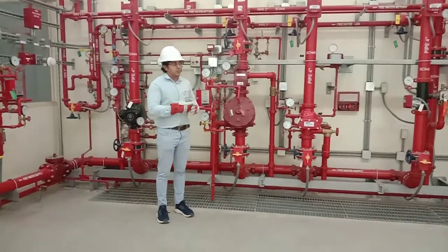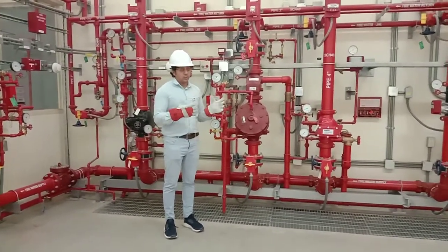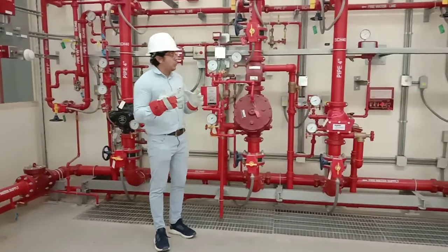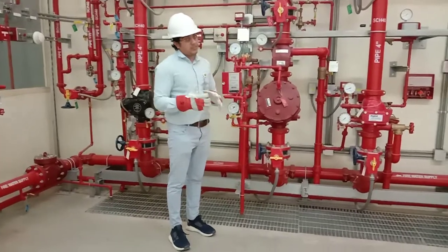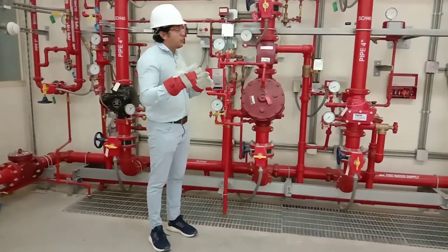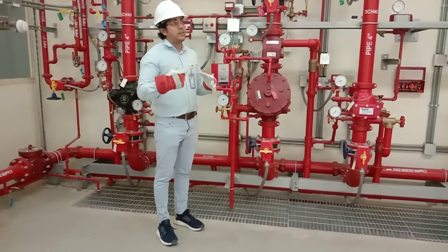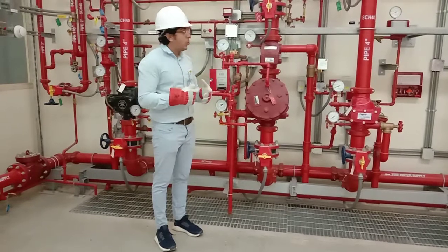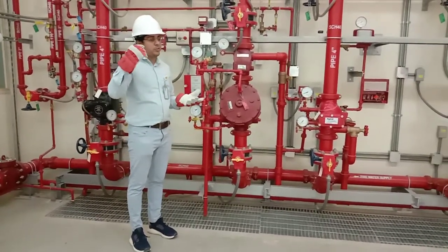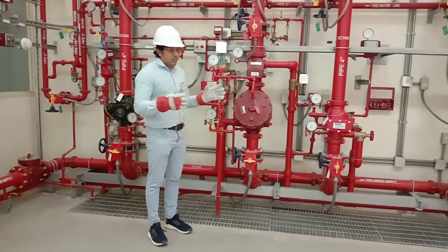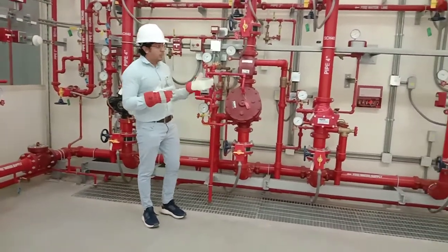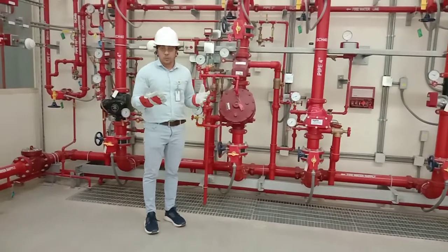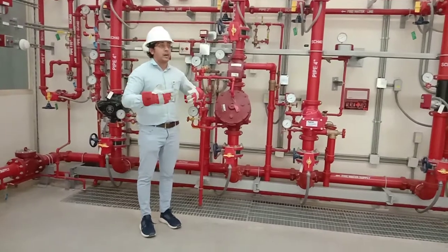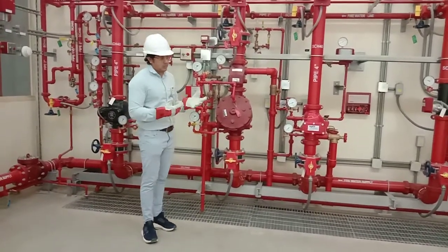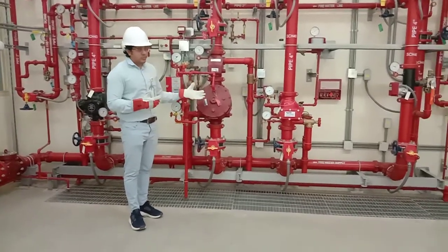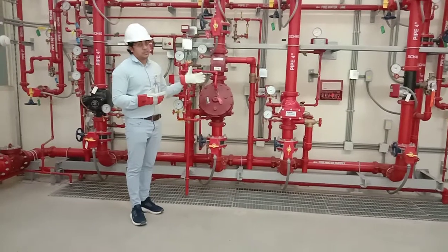Normally, we want to install a pre-action system in those locations, those buildings, where we want to avoid the room getting damaged by water, right? We don't want to discharge water without fire. For example, if someone mistakenly breaks a sprinkler, water discharges, or maybe due to some mistake the valve is tripped and water discharges. No, we cannot discharge water like this in those conditions. Normally, the applications are museums, historical rooms, libraries, electronics rooms, and electronic data centers where highly costly materials are stored. In those areas, we don't want to activate a sprinkler system without fire.